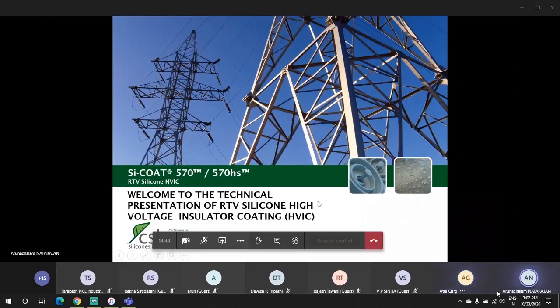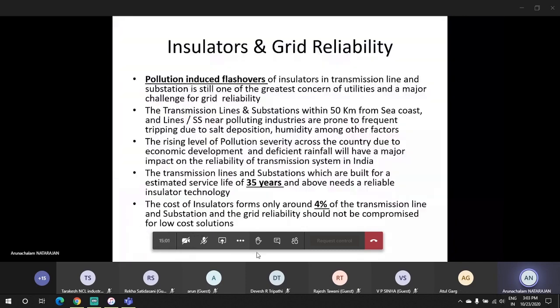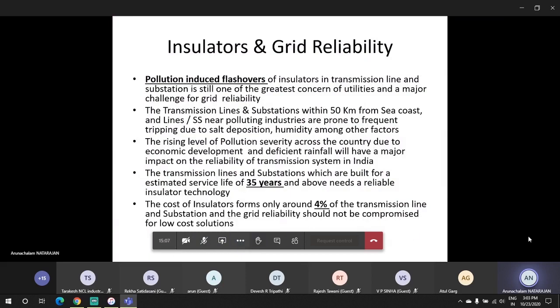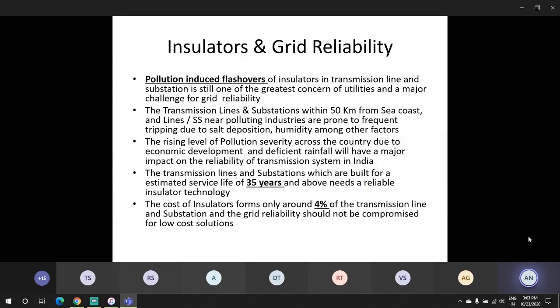So we will be covering this RTV silicon high voltage insulator coating. It will run for about 15 to 20 minutes, and please do not hesitate to stop me if you are looking for any clarifications. I will just give a brief overview on insulators and grid reliability. Pollution-induced flashover of insulators is one of the great concerns of all utilities and a major challenge for grid reliability, particularly the lines and substations within 50 kilometers from the sea coast and lines and substations near polluting industries, which are prone to tripping due to deposition, humidity, and other factors.